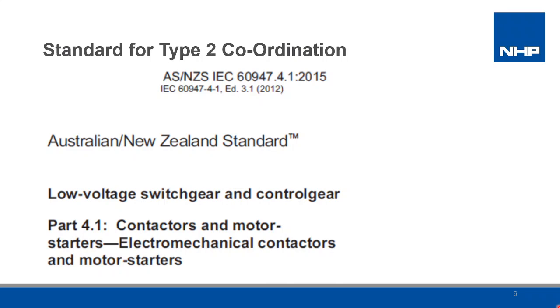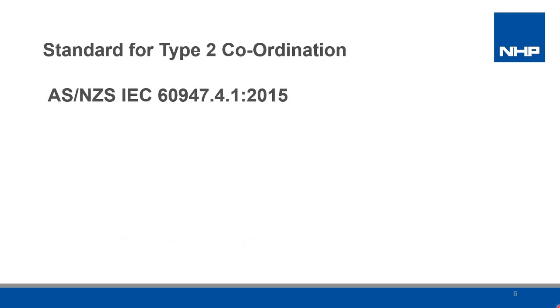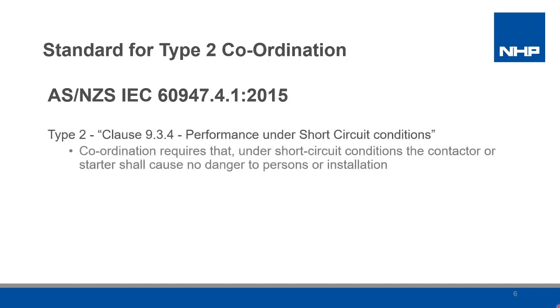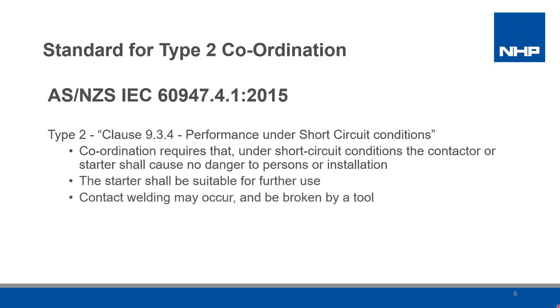AS/NZS 60947.4.1 is the standard for motor starters, and this defines the performance requirements for Type 1 and Type 2 coordination. With Type 1 coordination, it basically provides that the fault is interrupted safely without damage to other equipment or personnel, and the components, whether the contactor, overload or MCCB, are damaged, they could all be replaced prior to putting the motor starter back into service. Whereas with Type 2, the key points are safety as per Type 1. However, the starter shall be suitable for reuse without replacing components, and can be put back into service after the cause of the fault has been found and rectified. Welding of the contactor's contacts, provided the weld can be broken by a tool without deforming the contact set, is okay and accepted by the standards.